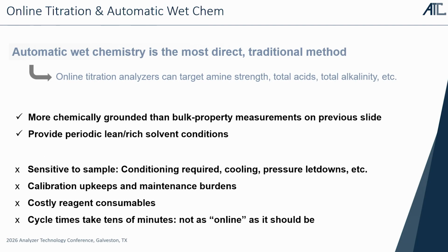So the most direct and traditional method that we've seen at these amine plants is automatic wet chemistry. These online titration analyzers can do lots of things, like target the amine strength. So how much capacity does that amine solvent have left? Total acids, the pH of it, obviously, is a good one. And it's way more chemically grounded than the bulk property measurements that we went over on the previous slide. And these actually can provide those periodic conditions of the amine. But it's very sensitive to the sample.